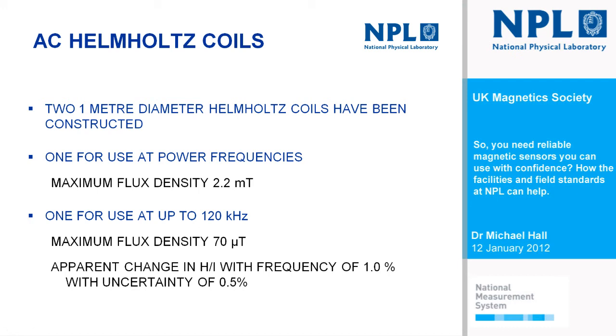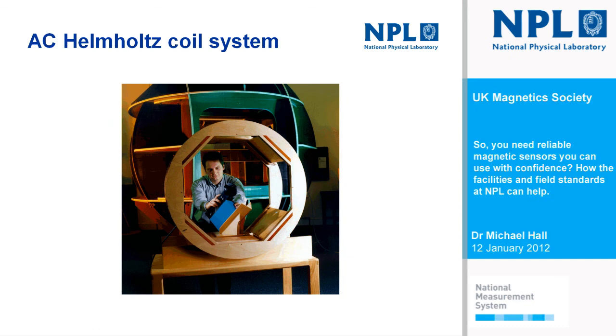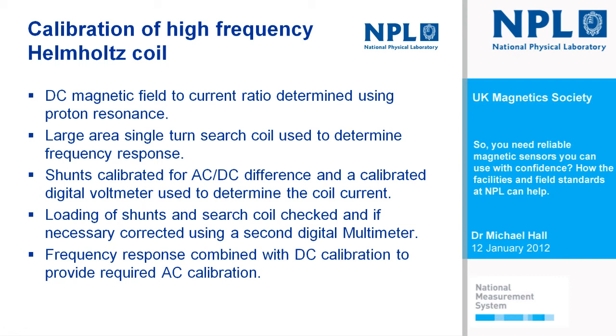So how do we calibrate the high frequency Helmholtz coil? Well, we're in the low magnetic field lab, so we do a DC calibration of the field to current ratio, and that is done inside the cancelled environment, so we have a very low uncertainty on that. We then use a large area single turn search coil, and we don't have to worry about the fact that the field through that is not uniform for the whole area, because we're only interested in the frequency response. The fact that it's single turn is the important thing. It's big enough to give enough output to measure with low uncertainty, and because it's single turn, there's no intra-winding capacitance that's going to give us any frequency dependence on the effective area of that coil.